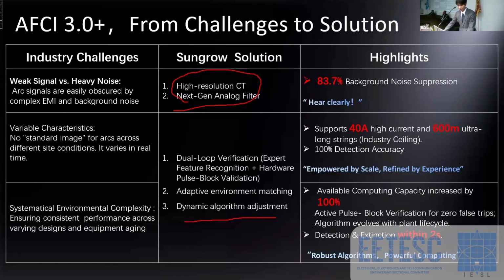As I said, the high resolution CT and the new analog filter will introduce more than 83% background noise suppression. It makes the system hear the noise clearly, and hear the arc fault clearly. And the second is the empowerability, like 40 ampere and 600 meters. It's a really good choice for large scale PV plants. And for the last one, we can detect and extinguish within 2 seconds. So that's about the AFCI.